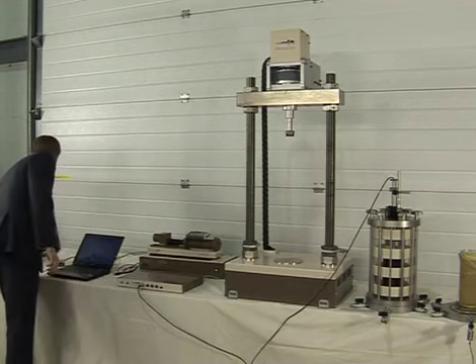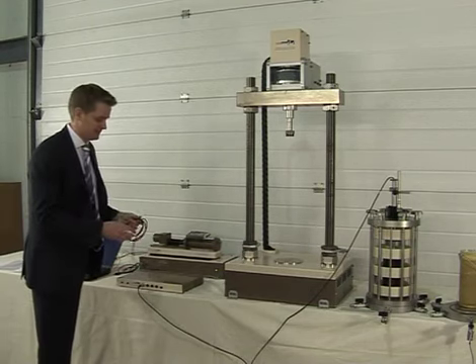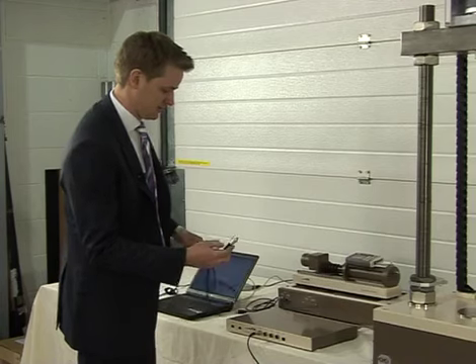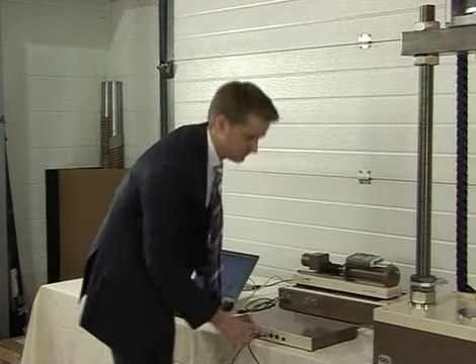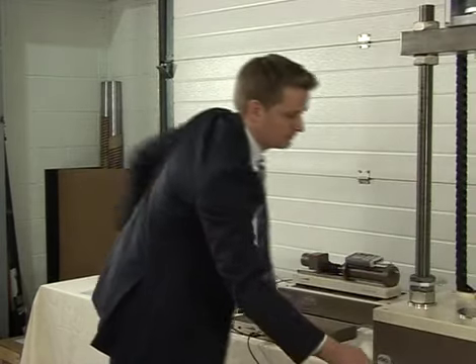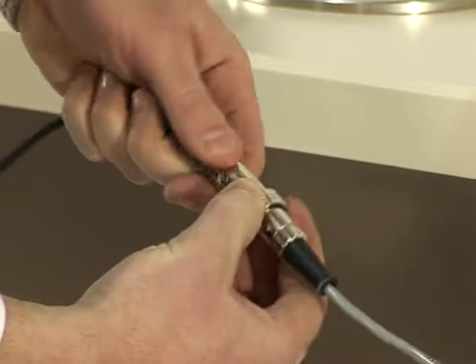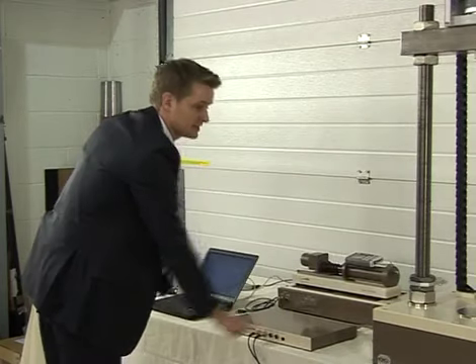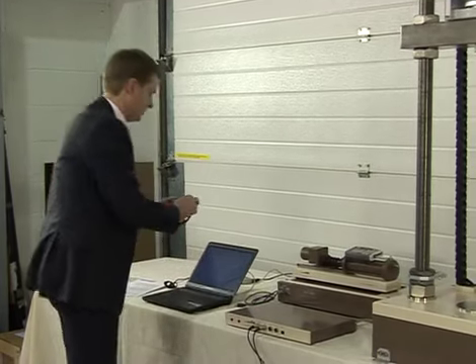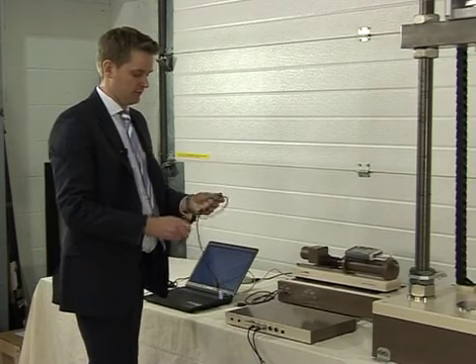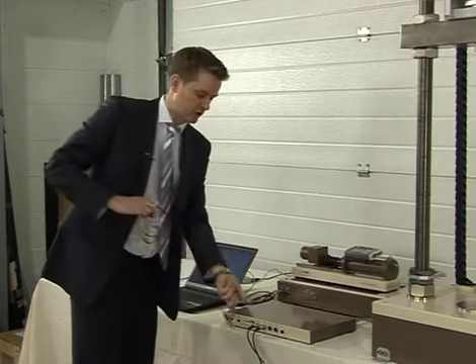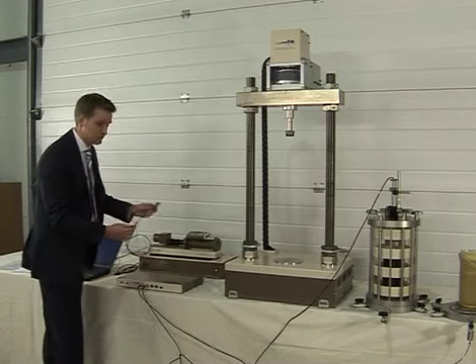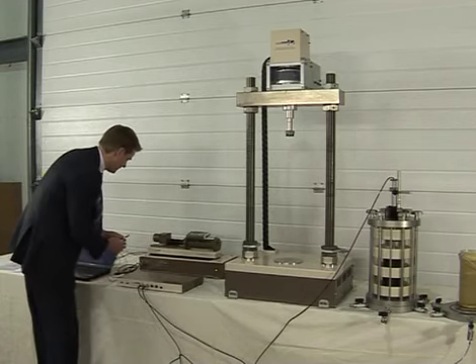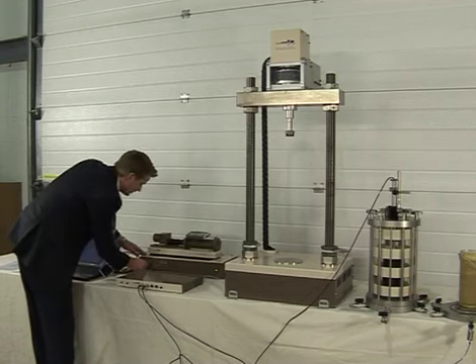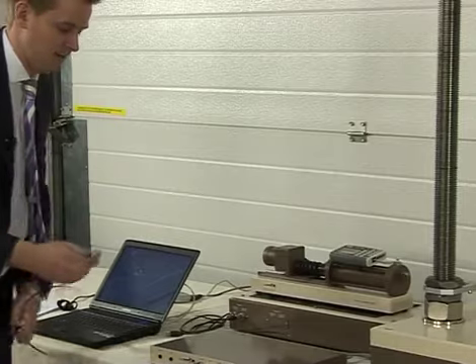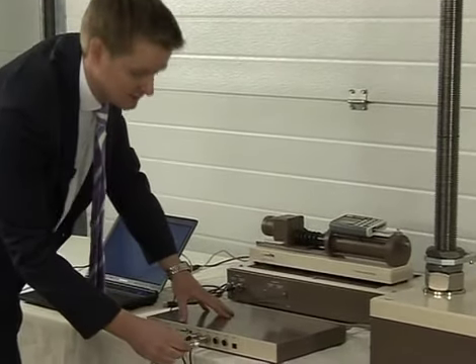The pressure transducer, this one I have an extension lead. The pressure transducer to channel 1. We're not going to have a secondary cell pressure transducer because I have a cell pressure output from the monitor of the pneumatic pressure controller. And the monitor cable has a 3-pin DIN and a 5-pin DIN. The 3-pin DIN goes in the front of the pneumatic pressure controller, and the 5-pin DIN is going to go into the 10-volt channel, channel 3.